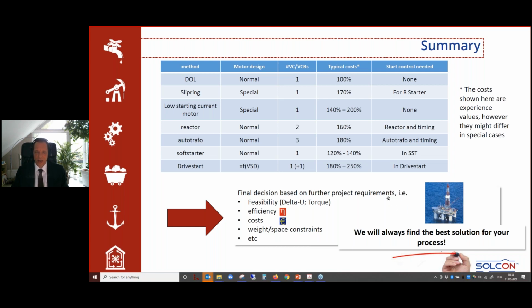If you have, let's say, a requirement that you are on a platform and you have space constraints, you might not have the luxury to install an additional starter because you have limited space. You might want to accommodate it in the electric motor and you choose the low starting current motor, which has a worse efficiency. On a platform with availability and with part counts, it might not matter. If you have air separation, where the only input value is electrical energy, efficiency is in fact the topic here. There you will choose a starter that is not affecting the motor efficiency, and you might land in a different starting method. The thing is, we are always looking out for our customers to find the best starting solution, and it might differ from case to case.